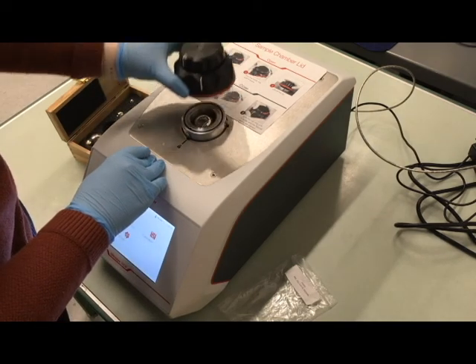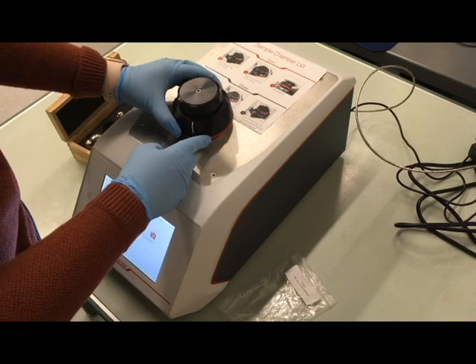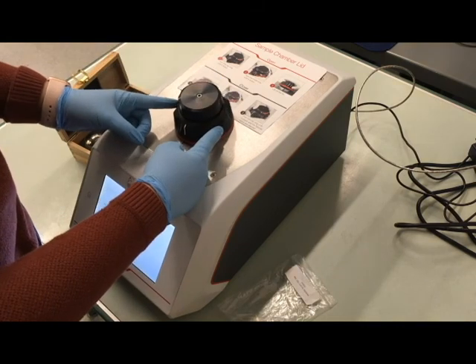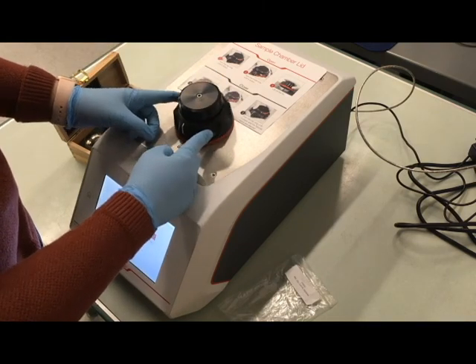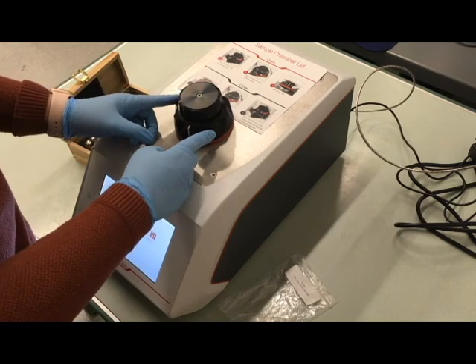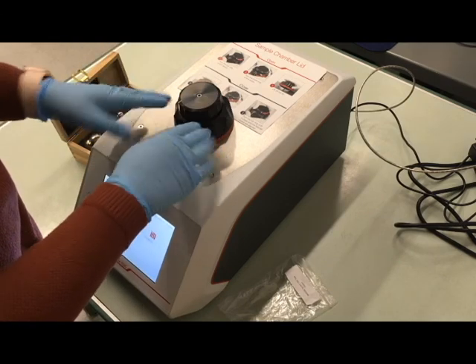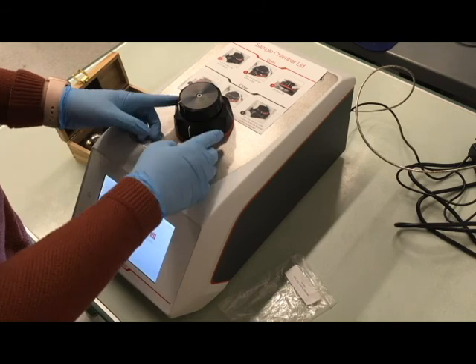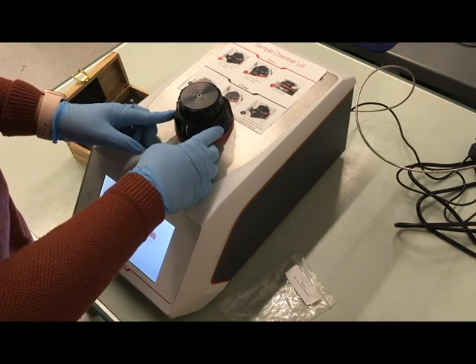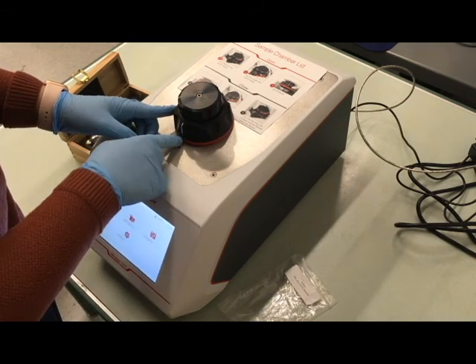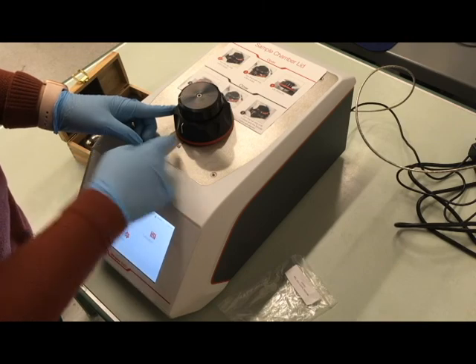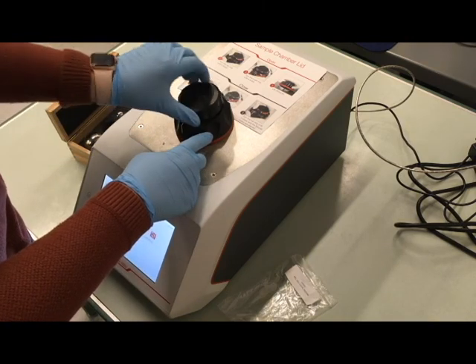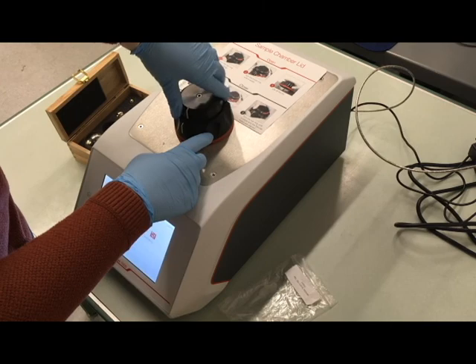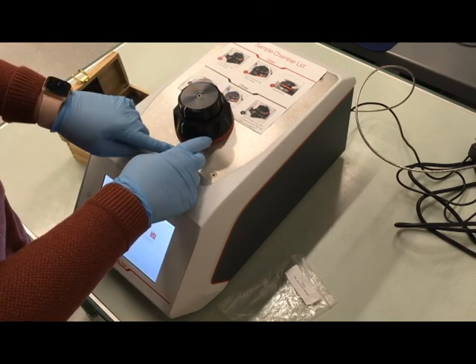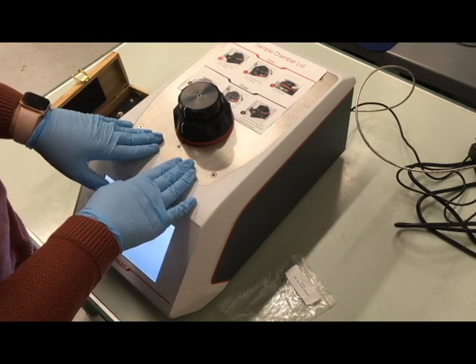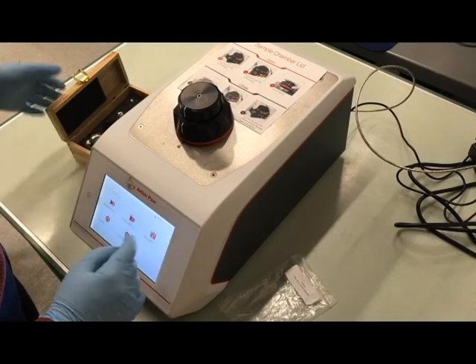Next, I'm going to put the lid on by just doing the inverse of what I did earlier. This should rotate very, very easily. If this is not rotating easily, the lid needs to be pulled off and set back down again because it's a little sideways, which is pretty easy to do. So we're just going to rotate that until the white line lines up with the lock there, and then we're going to rotate the top until it lines up as well. So now my sample is inside the machine, and I'm going to go to the screen to set up my calibration run.